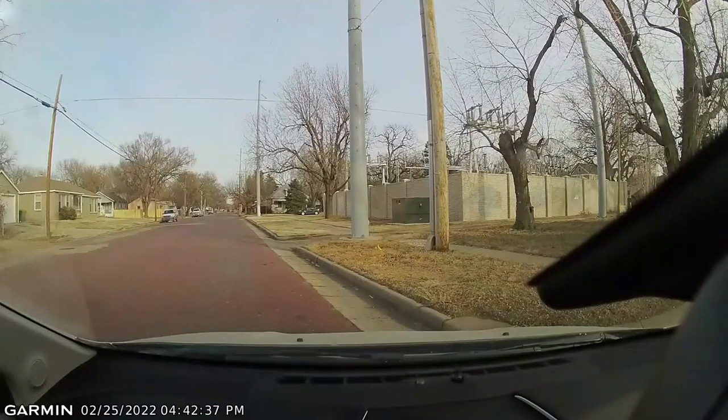Right in front of us here, we have a wooden pole, and it picks up what's called distribution coming out of the substation, and then it goes on the poles that go behind your house to the transformers that reduce the power to the 120 volt or 240 volt power that comes into your house. The distribution lines that go from this substation out to the houses, I think they're about 7,200 volts, and they may have as much as 3 energized wires at that voltage that go to the various transformers behind people's houses.